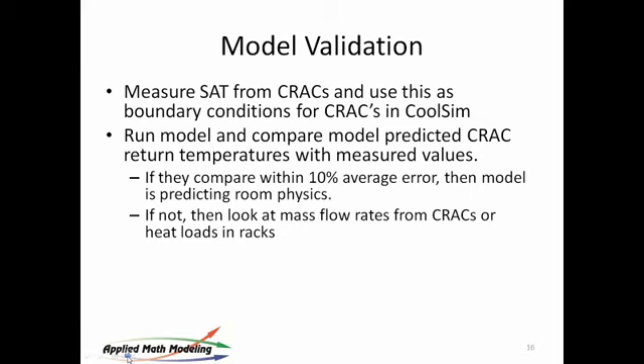So the way that we validate models, the easiest way that I have found to do it, is to measure the supply air temperature coming from the cooling units and use this as a boundary condition for the CRAC units in the CoolSim application. That bounds the situation, it bounds the problem. So what we do is we ask the customer, or we measure what the cold air temp is.